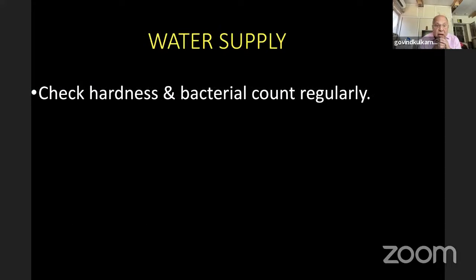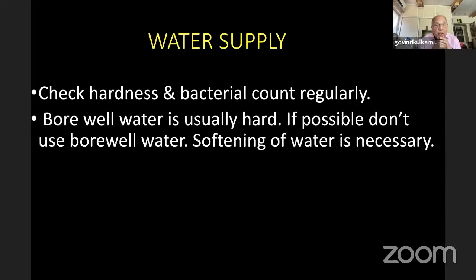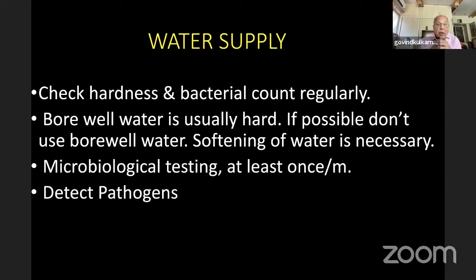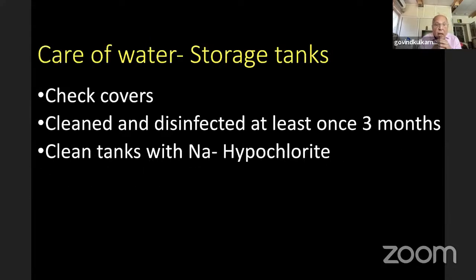Water supply. Check the hardness and bacterial count regularly of the water you are using in the OR. Borewell water is usually hard. If possible, don't use borewell water, but if you have to use it, then softening of the water is necessary. Microbiological testing of the water should be done at least once a month to detect pathogens. Care of water storage tanks must be done regularly and should be checked.